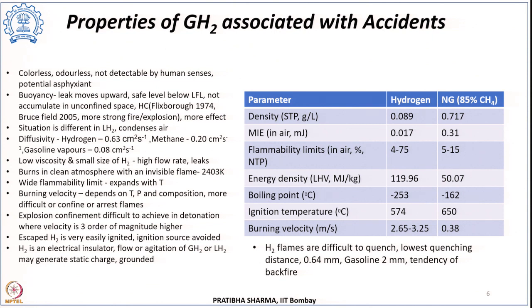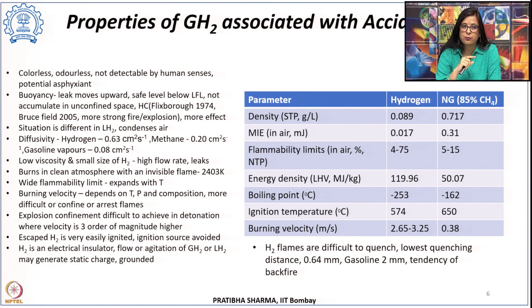These are some of the properties where hydrogen has been compared with natural gas, with an order of magnitude difference in density and other parameters. Hydrogen has a low viscosity, and together with its small molecular size, it becomes very easy for hydrogen to achieve very high flow rates in case of any leak occurring at piping, fittings, seals, or valves — resulting in very fast escape of hydrogen.